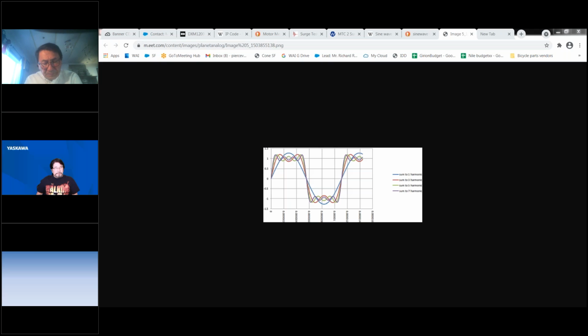So the solution, if you're using a standard VFD, you're going to have to use a sine wave filter to get the full life out of your submersible motor. No ifs, ands, or buts about it, I think. And I think that the manufacturers on both sides are coming out and agreeing with that. Certainly, if the statements are such that we're not honoring warranty until you put a sine wave filter on the output of the VFD, that's a pretty conclusive statement. So moving on, Craig is right.